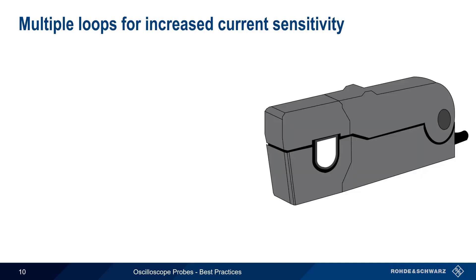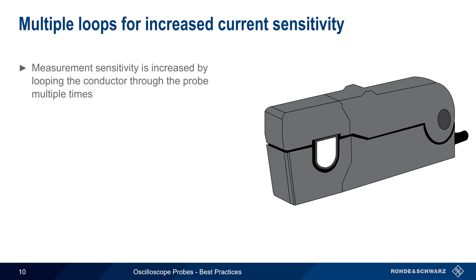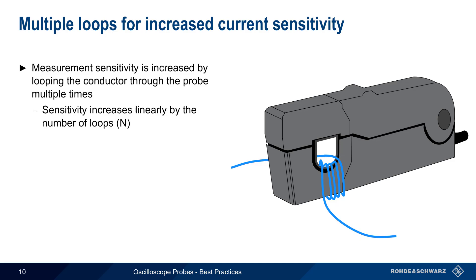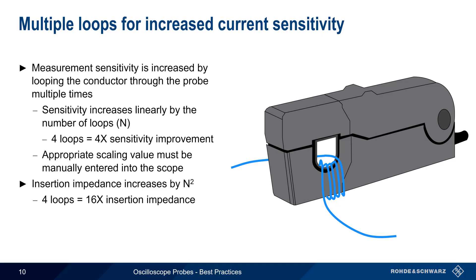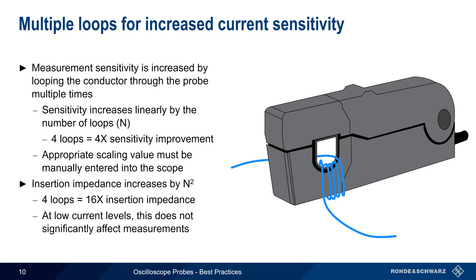Another tip regarding current probes is how to increase current measurement sensitivity. One technique is looping the conductor through the probe multiple times. The sensitivity of the probe increases linearly with the number of loops — looping the conductor through four times improves sensitivity by a factor of four. Since the scope has no way to know how many times the conductor has been looped, an appropriate scaling value must be manually entered into the scope. These loops also increase the insertion impedance by the square of the number of loops, so four loops would increase the insertion impedance by a factor of 16. However, this increased insertion impedance is usually still quite small and does not significantly affect measurements at low current levels.